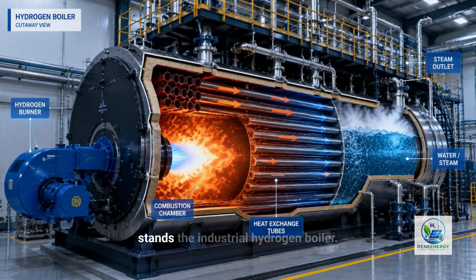At the center of the boiler house stands the industrial hydrogen boiler. From the outside, it looks like a massive pressure vessel wrapped in insulation and surrounded by piping. Inside, however, is an intricate engineering system designed to transfer enormous amounts of heat into water. Unlike residential boilers that heat buildings, industrial boilers generate large quantities of hot water or steam for manufacturing processes. When powered by hydrogen instead of natural gas, the fundamental objective remains the same: produce reliable industrial heat, but with the potential for dramatically lower carbon emissions. The real engineering story begins inside this steel vessel.